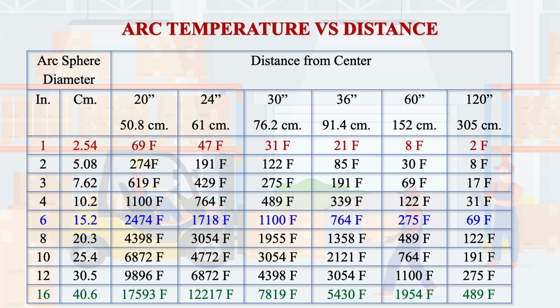We see the last line: if the sphere diameter is 16 inches, then what happens? At 20 inches, 17,593 degrees Fahrenheit will be felt, and this is an extremely serious temperature that can severely burn any person within the vicinity of 20 inches. However, it will go down if the distance increases to 120 inches, then it will be approximately 500 degrees Fahrenheit, which is still dangerous, as it can burn a person within the vicinity of 120 inches. Now, some of the hazards from the power arc and safety precautions we will discuss.